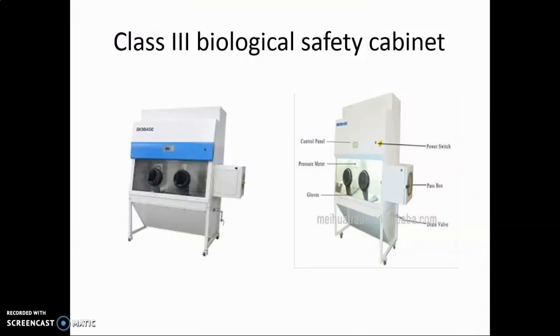The class 3 biological safety cabinet was designed for work with biosafety level 4 (BSL4) microbiological agents and provides maximum protection to the environment and the worker. It is a gas tight enclosure with a non-opening, completely sealed viewing window.